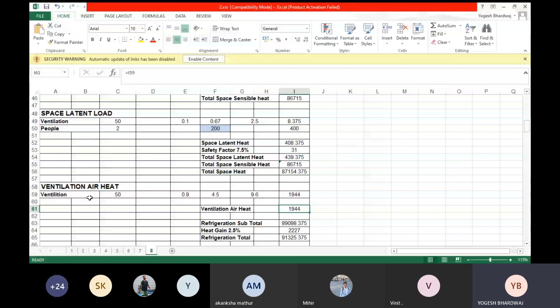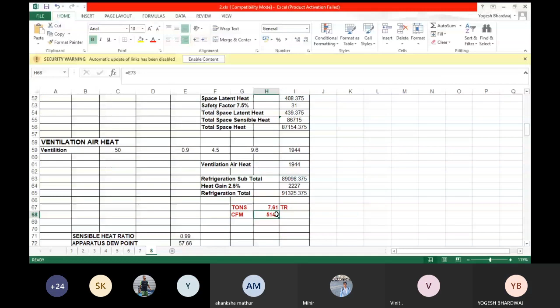This is the heat. So this is the total heat, which is the sum of sensible load plus sum of latent loads plus sum of ventilation load. And this is the CFM. So how it is calculating the CFM, that I will show you now. Okay. Before calculating the CFM, I need to calculate the ADP. So how can I calculate the ADP?